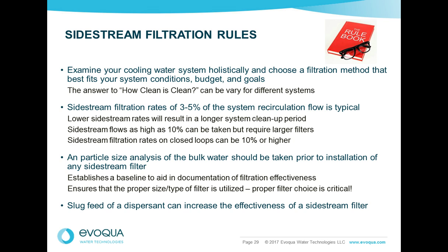In general, in sizing a filter, you should take 3 to 5% of the system recirc rate. Normally that amount is going to be effective in cleaning up and maintaining the cleanliness of your system. You may have to go to a larger flow due to the particulate loading on your system. But remember, as you go larger, the filter cost is going to increase. And as Bob mentioned earlier, if you're next to a construction area or a farm, your loading is going to be higher. So you're going to want to go a little bit higher and oversize that filter a little bit.